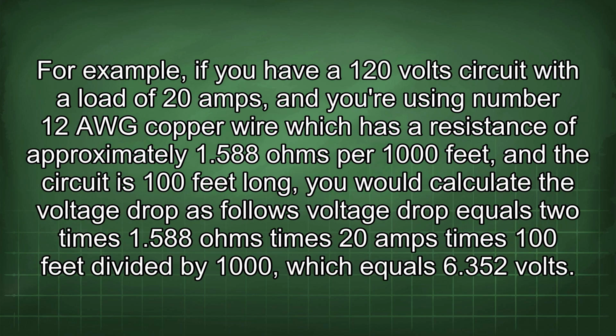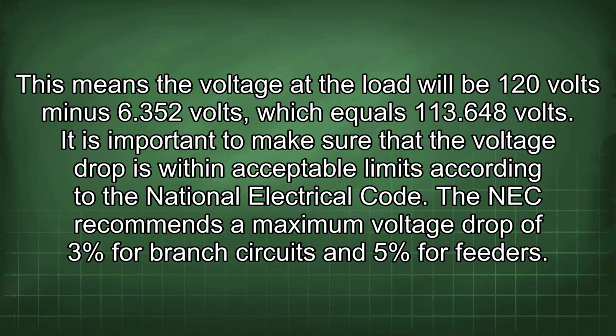For example, if you have a 120 volt circuit with a load of 20 amps and you're using number 12 AWG copper wire, which has a resistance of approximately 1.588 ohms per 1000 feet, and the circuit is 100 feet long, you would calculate the voltage drop as follows. Voltage drop equals 2 times 1.588 ohms times 20 amps times 100 feet divided by 1000, which equals 6.352 volts. This means the voltage at the load will be 120 volts minus 6.352 volts, which equals 113.648 volts.